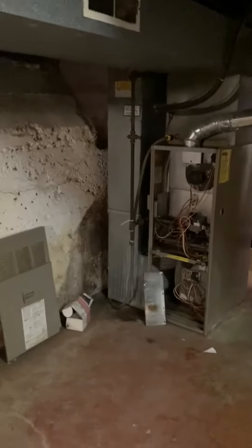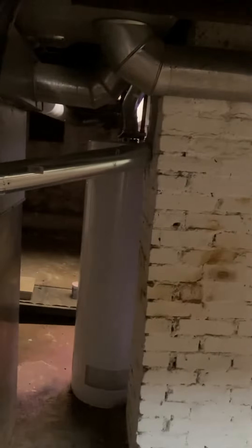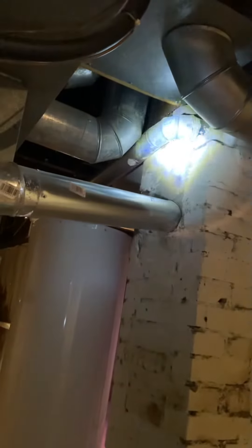In this basement we're focused on furnace-only replacement. You can see we're set up for 80% efficiency — we've got the four-inch flue going into a masonry stack, right in the middle of the house. There's also a three-inch flue feeding the water heater at the same time.